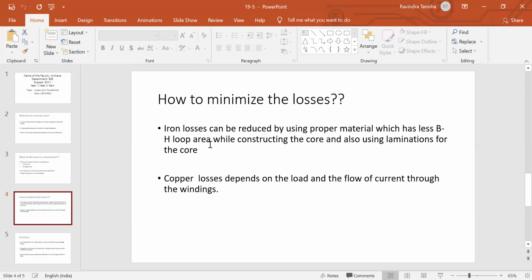Then how to reduce these losses? How to minimize these losses? These losses can be minimized if you use a proper material. For example, iron loss can be reduced by using a proper material which has less BH loop area. While designing the core part of the transformer, if you choose a material having less BH loop area, then obviously we can reduce the amount of iron loss, and in turn the amount of hysteresis loss. Then what about eddy current loss? How to minimize the eddy current loss?